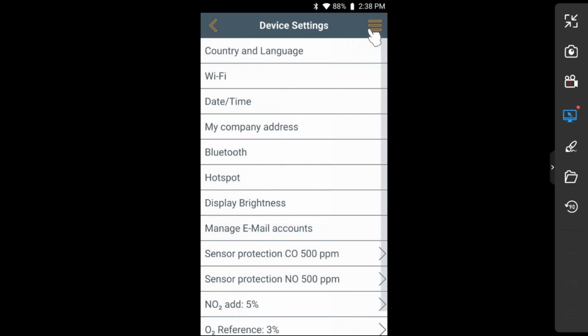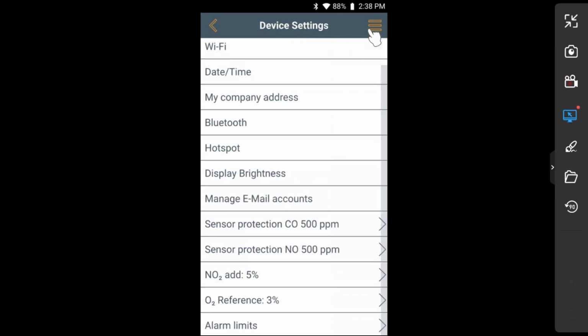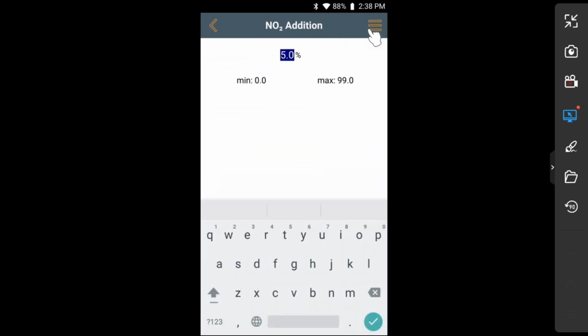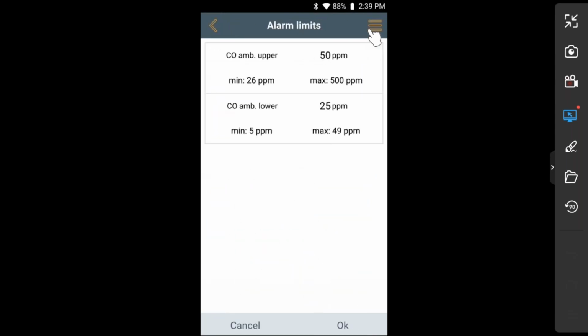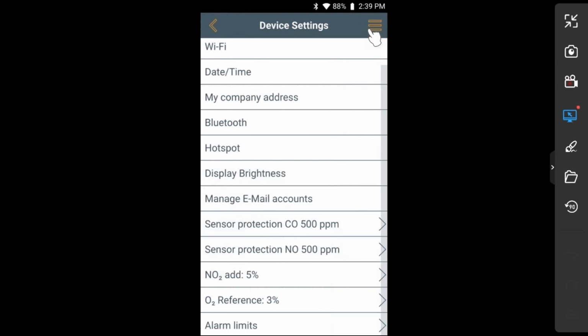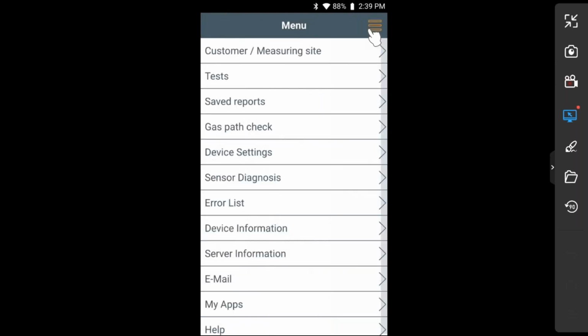You could do it with the NO sensor as well. And then when we talked about the NO2 adder, if you do have an NO sensor and you want to add an extra 5% to get the NOx, you can do that by just putting in 5%, 3%. It's factory set, I believe, at 5%. So, alarm limits. These are the alarm limits that I set up when I was doing that CO ambient test. You can have not only a visual alarm, but also an audible alarm that alarms when you exceed a certain ppm of CO when you're doing primarily an ambient CO test.